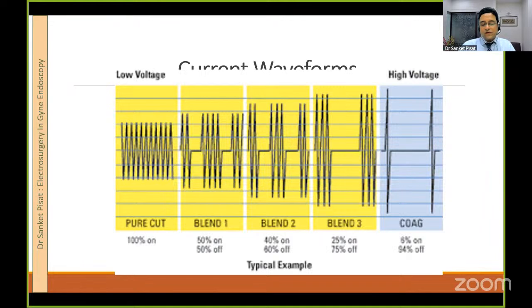How do the waveforms differ? This is the current waveform, with pure cutting current on the left and coagulating current on the right. You can see in the pure cutting waveform, the amplitude of the waveform is less. That means the up-down strokes are less, but the waves appear at more frequent intervals. So you have a waveform appearing at a higher frequency, but at a lesser amplitude. And if you look at the right of the picture, this is the same waveform, but it has a much higher amplitude and a lesser frequency.